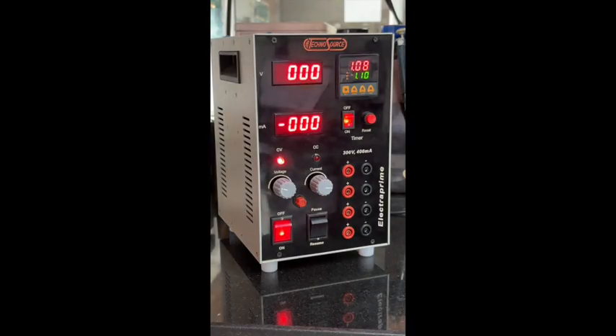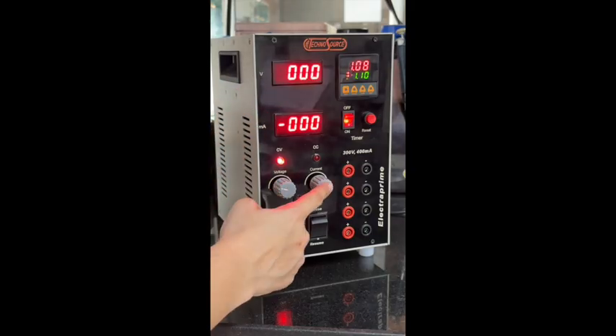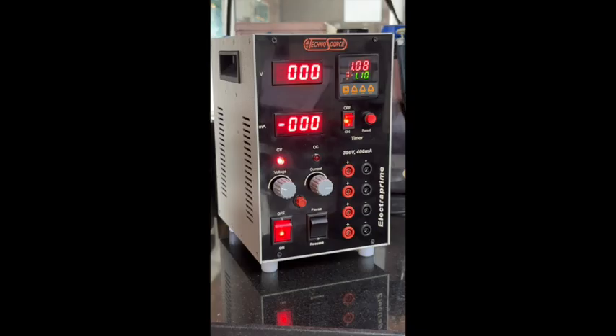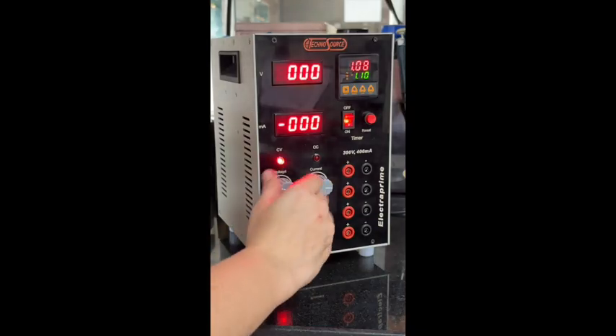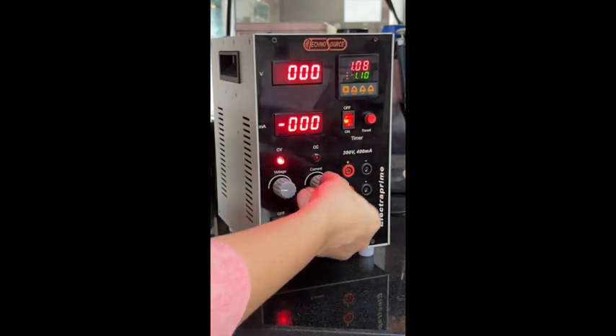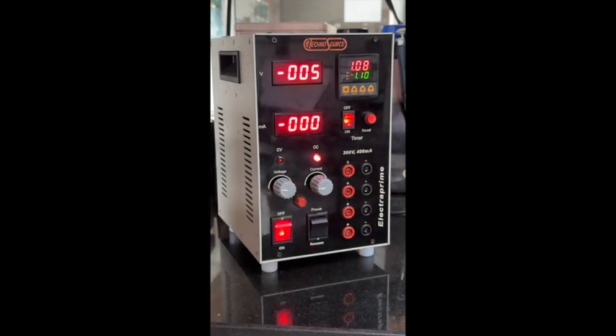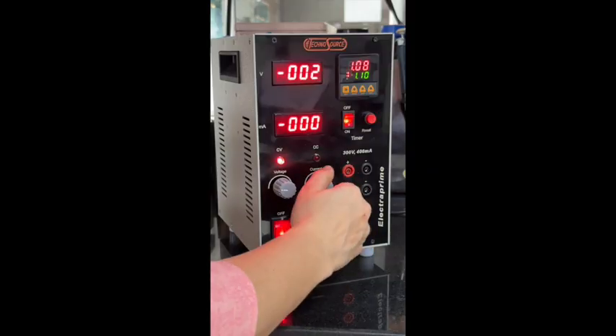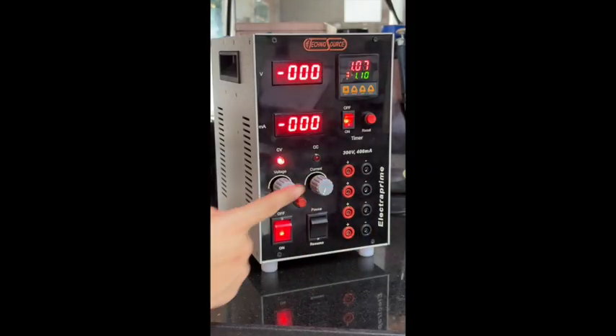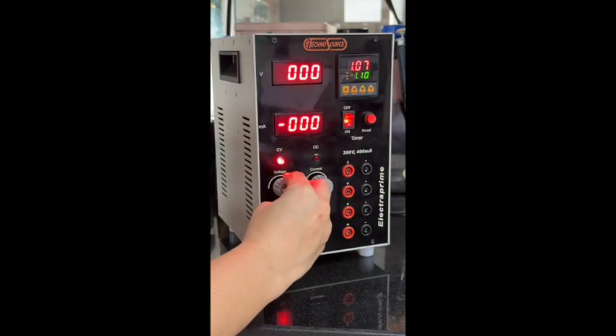The other reason for the displays to show 0 is that the voltage and current knobs are not adjusted. Turn both knobs counterclockwise. To adjust in CV mode, turn the current knob clockwise till the end. Now adjust the voltage knob to the desired voltage.